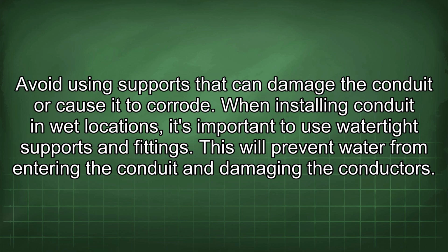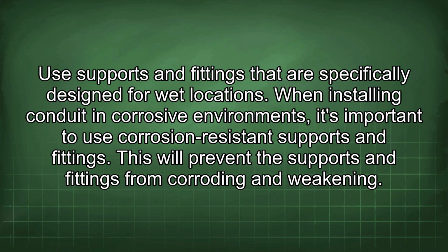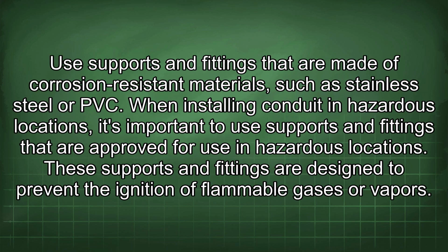When installing conduit in wet locations, it's important to use watertight supports and fittings. This will prevent water from entering the conduit and damaging the conductors. Use supports and fittings that are specifically designed for wet locations. When installing conduit in corrosive environments, it's important to use corrosion-resistant supports and fittings. This will prevent the supports and fittings from corroding and weakening. Use supports and fittings that are made of corrosion-resistant materials, such as stainless steel or PVC.